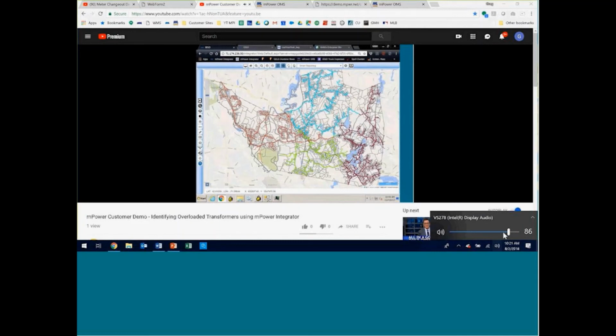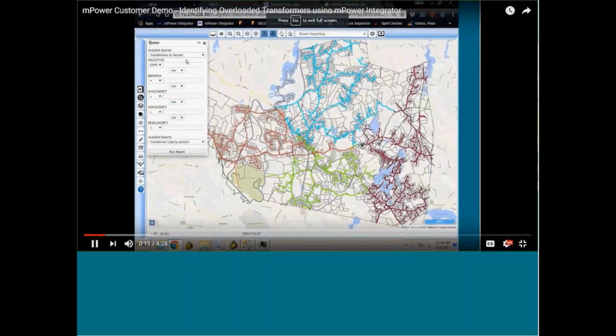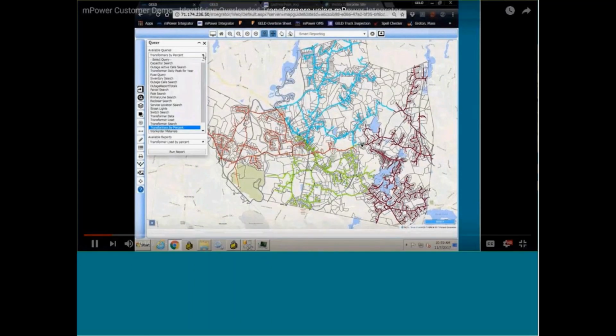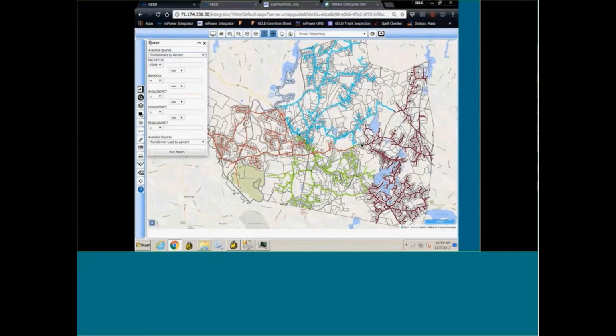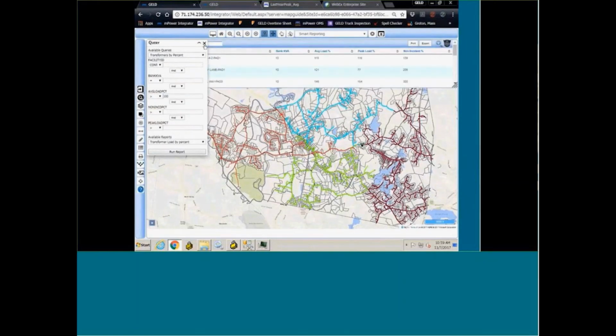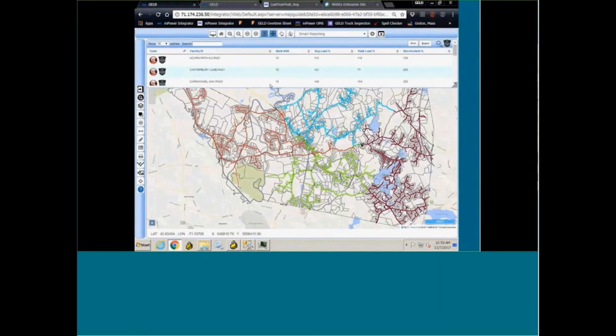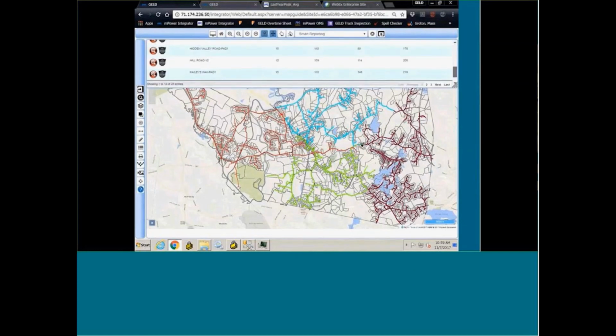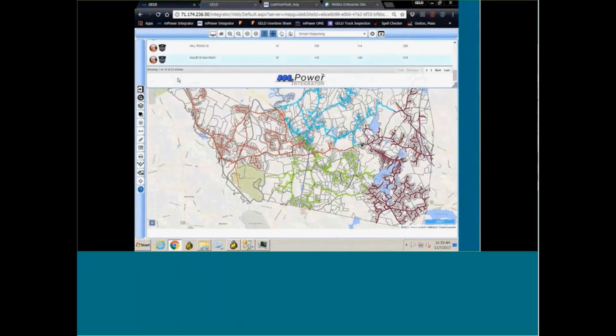One of the first important things we did once we linked our AMR system with our GIS system was to look at all the transformers that were overloaded. To find overloaded transformers, we run a query—we have a whole list of queries here. We can go to transformers by percent, and if we look at average load, that's the 24 hours in a day the way we have the report set up. So these transformers are the ones in our system on our peak day that had a load higher than 100%. Right now, we have 23 transformers in our system where the peak day this year went over 100%.